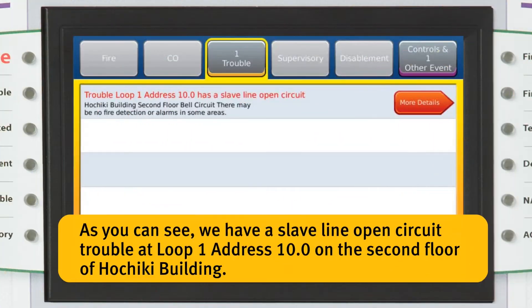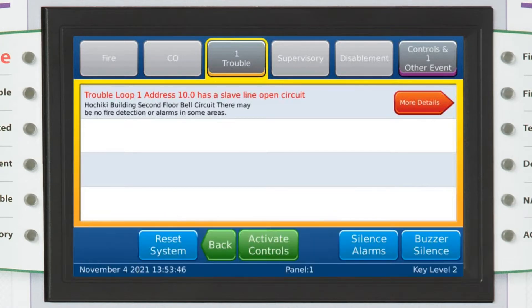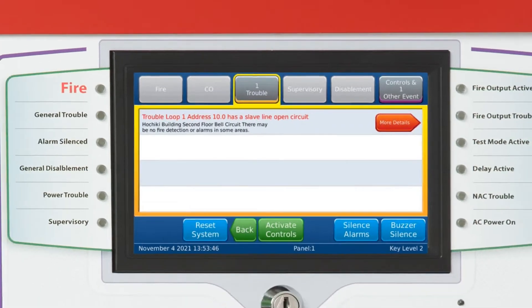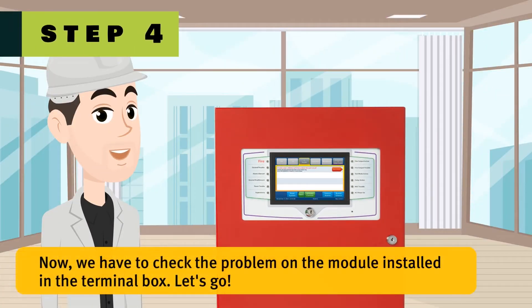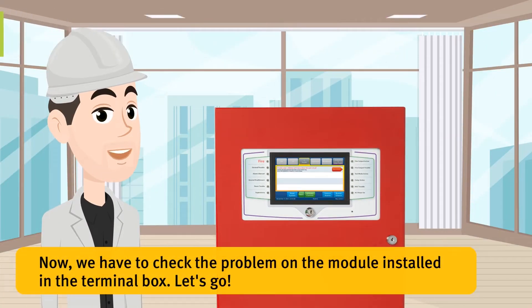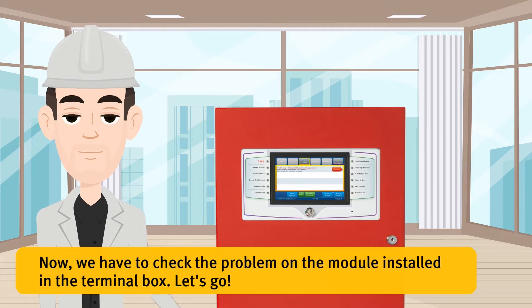As you can see, we have a slave line open circuit trouble at loop 1, address 10, on the second floor of Hochiki building. Now we have to check the problem on the module installed in the terminal box.